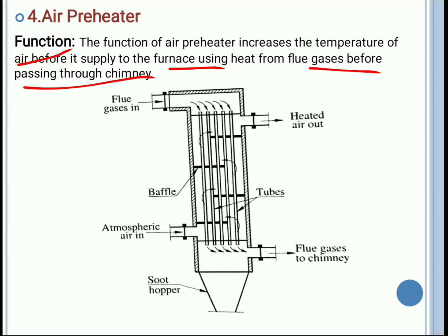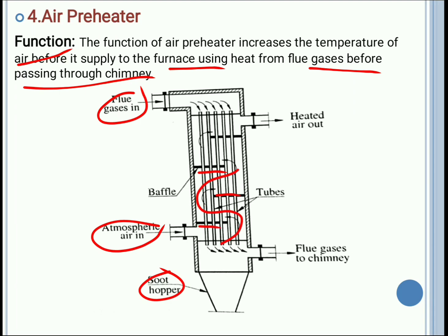This is the construction of air preheater. It consists of a soot hopper. There will be a pipe inside the air preheater. The flue gases are moved inside this pipe whereas the atmospheric air will move outside this pipe. The atmospheric air will enter from the bottom and it will travel outside the flue gases which are inside the pipe. Baffles are provided in order to direct the atmospheric air in a particular direction, which will increase the contact area, or contact time, between the atmospheric air and the flue gases.